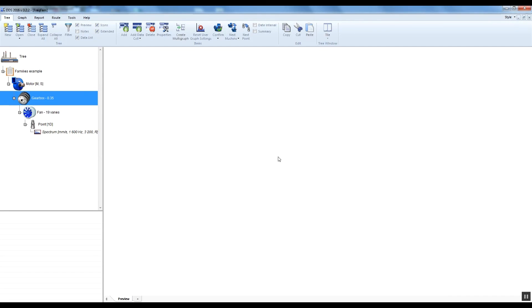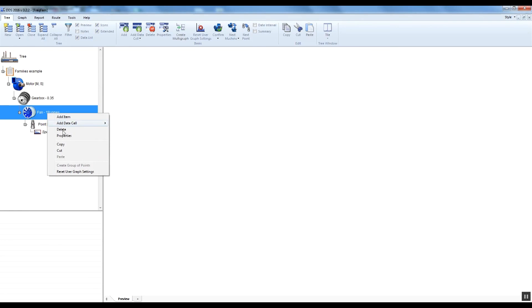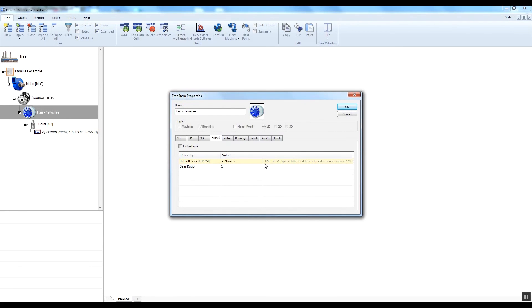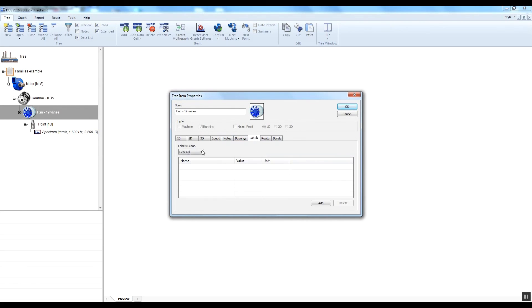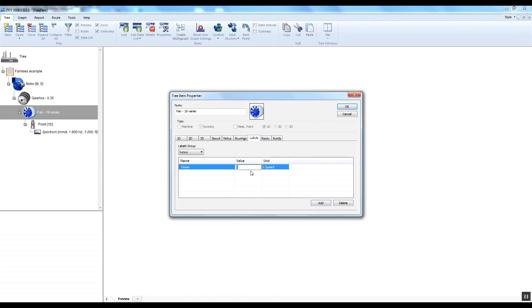Now we will enter the properties of the fan. The fan contains 19 vanes. I select the fan item and open the properties. The speed is 1050 RPM, which is inherited from the gearbox. I select the labels tab and select the vanes labels group. I press Add and enter the name of the new label: vanes. Now I enter the value 19, then select multiplying by the speed item and confirm by OK.